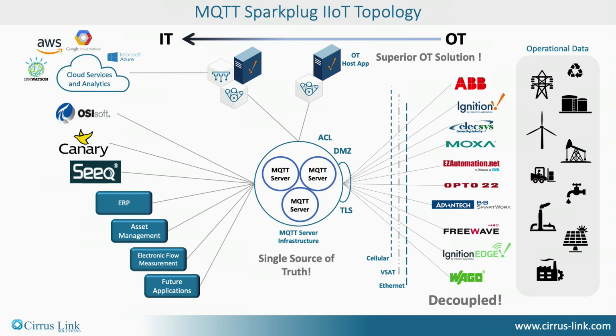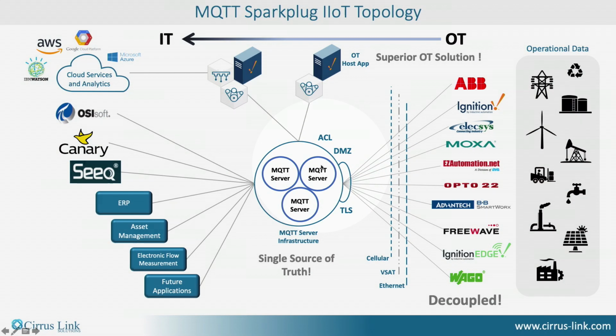The Sparkplug spec gives you quality for every tag that you're publishing. So I could have a good state on my edge of network box that says I'm connected, but the tag coming from my HART transmitter says it's last known good because my HART comms failed. So you've got the metadata you need within the Sparkplug spec to go all the way down to a tag level. If you had multiple devices on that edge controller, you're going to know the state of each of those devices, the state of all their tags, and the state of your connection from these devices into your MQTT servers.